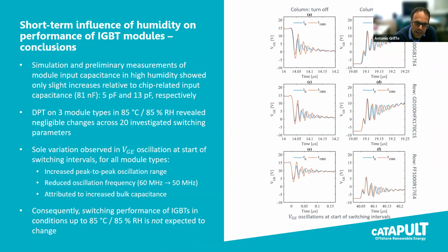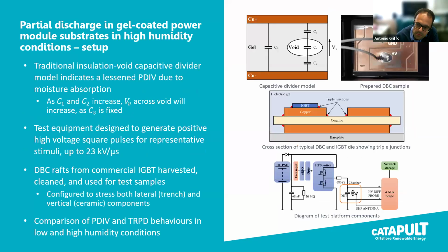Most show only a slight increase in the relative chip input capacitance. However, the effect of this on the switching transient is relatively minor, with only a slight slowing down and reduced oscillation frequencies in the gate-to-emitter voltages. This confirms that short-term effects of increased humidity penetration into power modules do not significantly affect the switching characteristics. But of course, this does not mean that the long-term effects are not significant. And this introduces the next topic. Next, please, which is the longer-term effects of humidity penetration on the reliability of power modules.